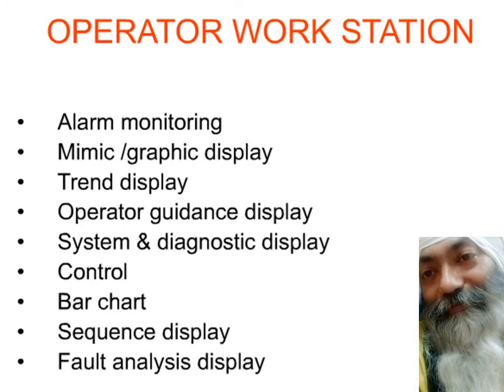The operator workstation has several facilities. First, there is alarm monitoring — if anything goes bad, whether the level, pressure, temperature, or flow goes out of range, an alarm is generated. The operator can navigate to that particular section or page. The entire plant may be divided into 30 sections displayed as graphic displays, also called mimic diagrams because they mimic the behavior of the plant.